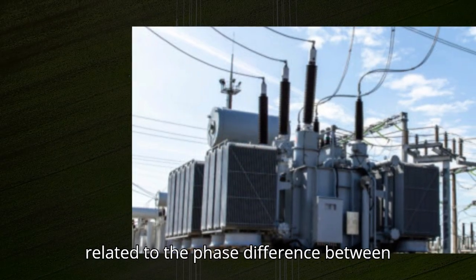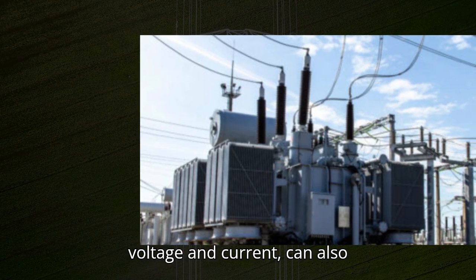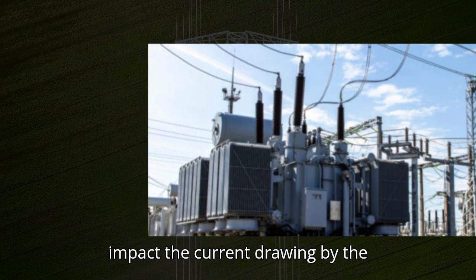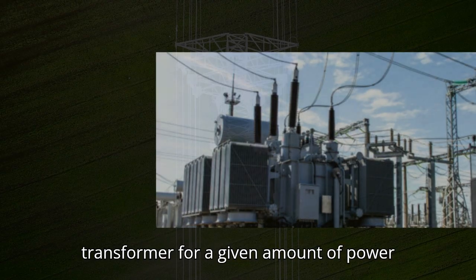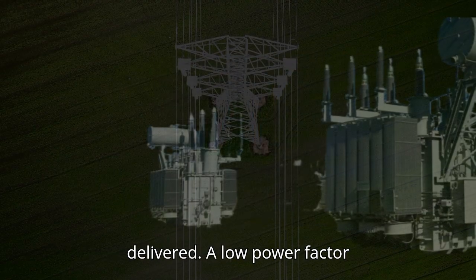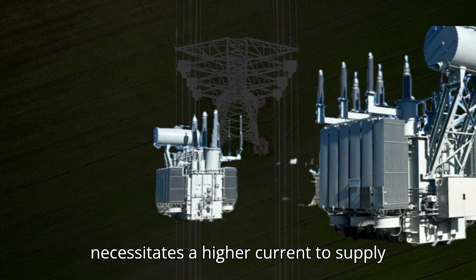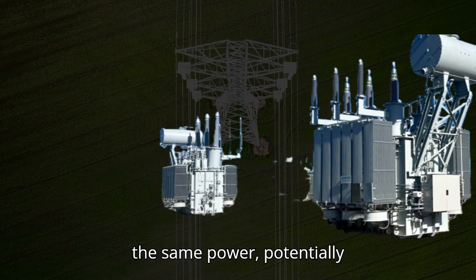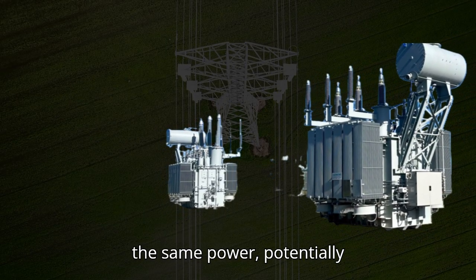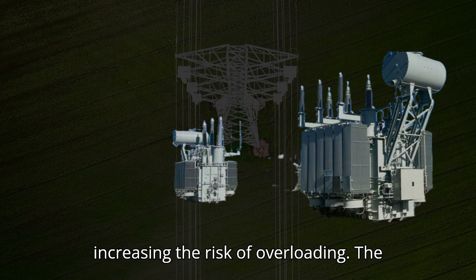Furthermore, the power factor of the load, which is related to the phase difference between voltage and current, can also impact the current drawn by the transformer for a given amount of power delivered. A low power factor necessitates a higher current to supply the same power, potentially increasing the risk of overloading.